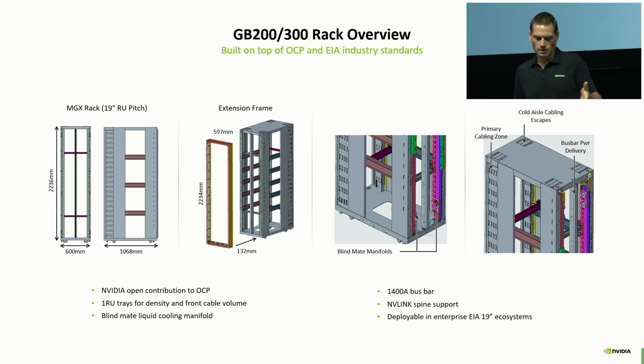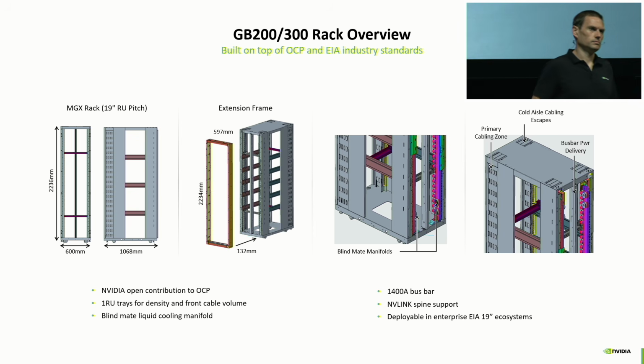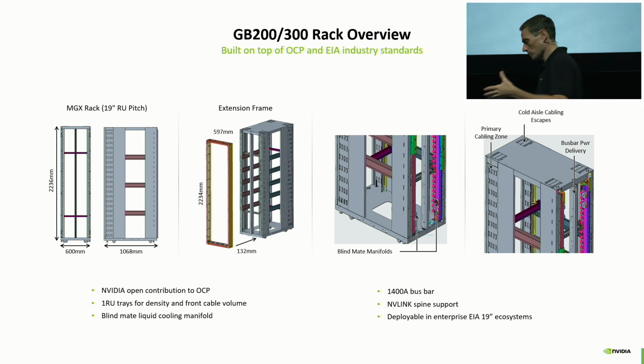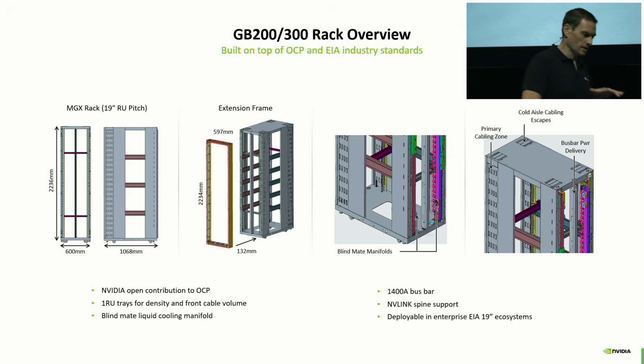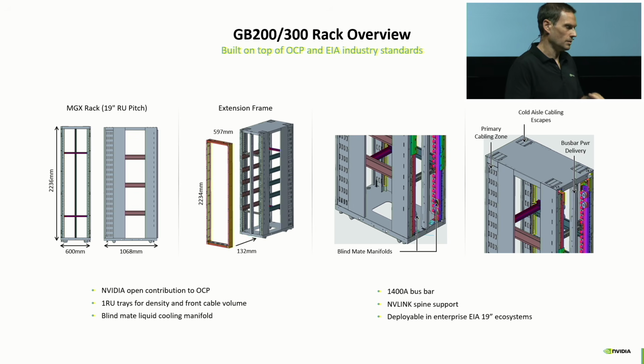In addition, we needed to support the power density through liquid cooling, and we needed a blind-mate set of manifolds to support that. There are other examples of blind-mate liquid cooling out there in the industry, but we didn't see anything that met our needs - not just around thermal capacity, where you have to drive a lot of fluid flow to support that 120 kilowatt number, but also at that tighter node density. So we created a new set of blind-mate manifolds to support that.